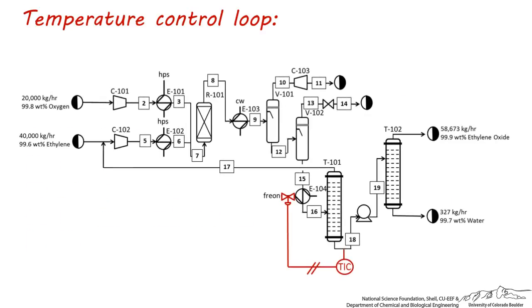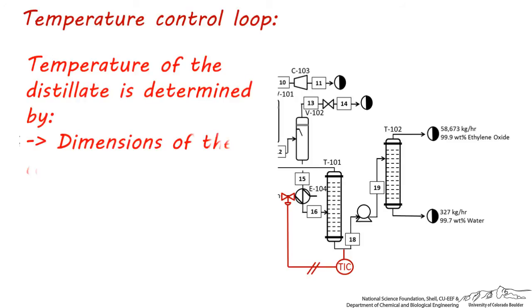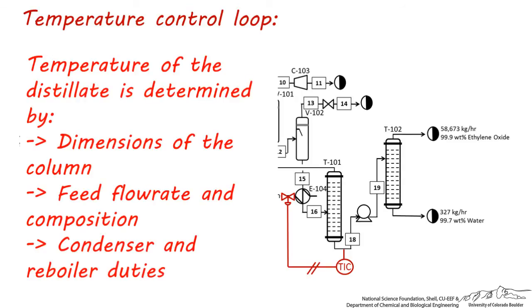Let's look at another example. Will this control loop adequately control the distillate stream temperature? Probably not, because you might remember from previous lectures that the temperature of the distillate and bottoms is determined by the design dimensions of the column, the feed flow rate and composition, and the condenser and reboiler duties. All of these factors are responsible for the temperature of the distillate stream. Distillate temperature is determined by the distillate concentration and condenser duty more than anything else, and therefore it can be difficult to control.